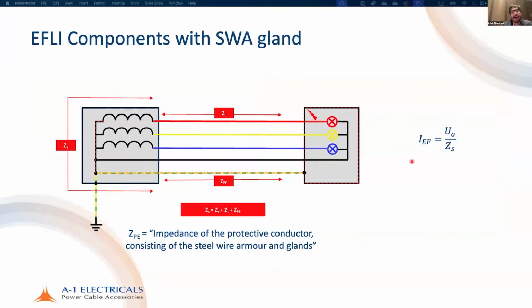See, when we use a steel wire armored cable gland, we have a continuous protective conductor running. So we are able to have a TN system. The impedance of the protective conductor consists of the steel wire armor and the gland itself. So there is enough. If the installation is designed correctly, enough earth fault current will flow. Automatic disconnection of supply will be very effective, right? Now, why is this important? Because the earth fault current is always the nominal voltage divided by this impedance, and this is a crucial part.